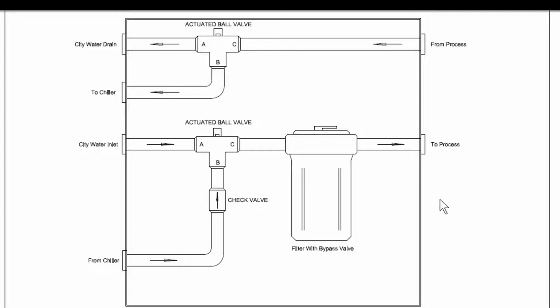Now, you also want to keep in mind, before you purchase one of these panels, the city water inlet temperature here, because some municipalities, and your local water district should be able to provide you with this, if they use what we call aerial storage tanks to store city water, those particular tanks can get quite hot during the summertime. So if your process requires 50 degrees, but your city inlet temperature can be 75, 80 degrees during the summertime, there's a good chunk of the year that you probably won't be able to use this panel. So you want to make sure you do that kind of research. All right, so that's a city water changeover panel.